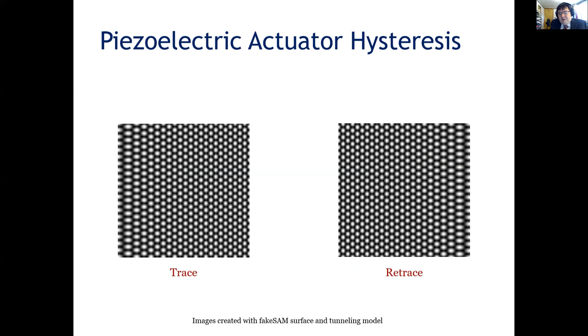So here's what it might do to an STM image. If you think of the left side as what the STM scan probe is doing, and the right side is what you see on your computer screen. So the controller is scanning the tip at what it thinks is constant velocity, but it's actually not constant. And so that causes one side to be stretched out and the other side to be squished. And exactly the opposite happens on the retrace. At the beginning, it's stretched out, and at the end, it's squished. And so you get images that are exaggerated here, but this is what might happen if you had hysteresis in your images. You can also have linear thermal drift. So I have a window that the STM scan controller is planning to trace, but if that window moves over the surface while I'm scanning it, then I get a distorted image.